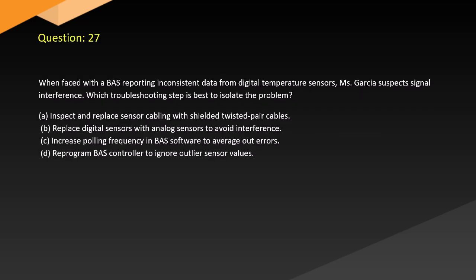Question 27. When faced with a BAS reporting inconsistent data from digital temperature sensors, Ms. Garcia suspects signal interference. Which troubleshooting step is best to isolate the problem? A. Inspect and replace sensor cabling with shielded twisted pair cables. B. Replace digital sensors with analog sensors to avoid interference. C. Increase polling frequency in BAS software to average out errors. D. Reprogram BAS controller to ignore outlier sensor values.